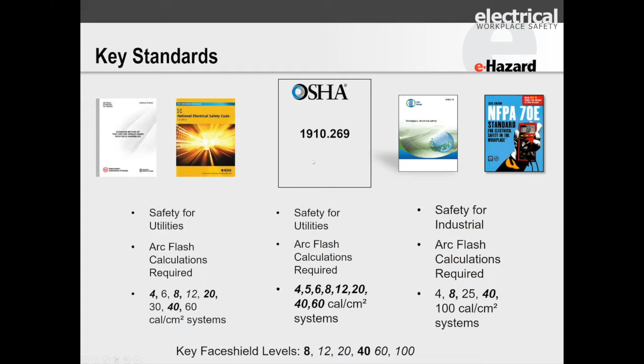Clothing ignitions are the number one killer in arc flash, and also the number one injurer. If you're wearing arc-rated clothing, even if it's only 4-calorie protection and you get into a 40-calorie event, you're most likely to live. If you get into a 40-calorie event in cotton or cotton-polyester clothing, you're more than likely to die or be severely injured. We'll talk about how that happens and why, although it may seem counterintuitive. So matching to the hazard is great, but at least getting into the basic gear is really important.